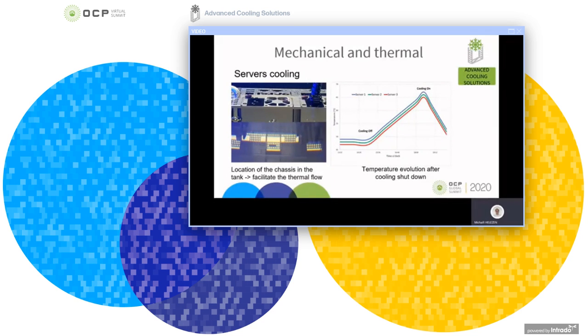One of our customers experienced such an issue. The temperature of the liquid rose and the servers failed before they could react. What is interesting is they told us that if they had had such a problem with their air equivalents, they would have changed many components in the following months, with all the costs that this implies. But with their servers submerged, there was no breakdown. The server continued to operate as if nothing had happened. The main reasons for this result are the homogeneity of the temperature in immersion and the gradual and slow rise in temperature. And for us, these are precious returns that confirm us in this technology.